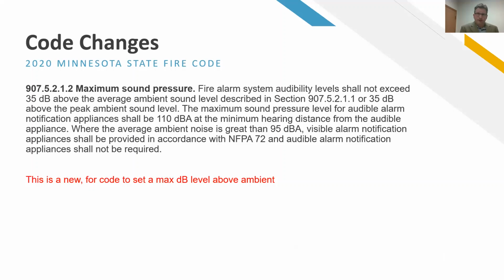Here's a section regarding how loud the fire alarm system has to be. There's a minimum we have to meet, 15 decibels over the ambient noise level. But now the code's putting a maximum too, you can only be loud to a certain extent. I think it's 35 decibels.